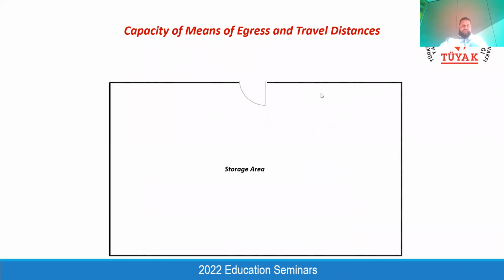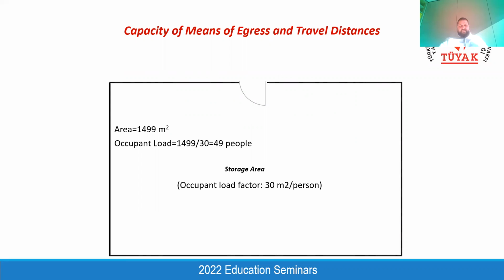I'm passing this one. For example, here you have a storage area. The area is less than 1,500 square meters, and the number of people is less than 50. It's okay if we fulfill the common path of travel distances. But when we exceed 50 people, as you remember, we need at least two remotely located escape doors.